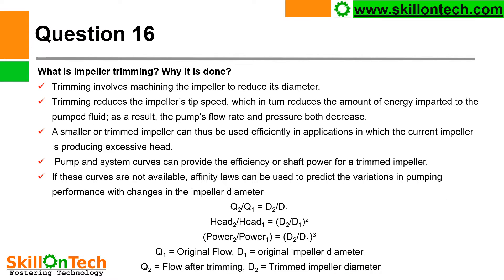What is impeller trimming and why is it done? Trimming involves machining the impeller to reduce its diameter. Trimming reduces the impeller tip velocity, which in turn reduces the amount of energy imparted to the pump fluid. As a result, both the pump flow rate and pressure decrease. A trimmed impeller can be used efficiently in applications where the current impeller is producing excessive head. Affinity laws can be used to predict the variation in pumping performance with changes in impeller diameter.